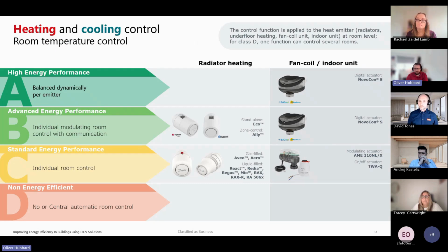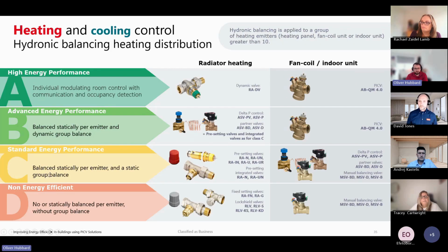So here we have a breakdown of what is actually in the actuator range and where they sit in terms of the new building automation and control standards. Things like the NovoCon actuators are in band A, smart TRV sensors in band B, and regular TRVs, thermal actuators or standard ABQM actuators are in band C. And when you look at it from the valve point of view, the dynamic balancing valves are in band A, and as you go down, you get back to regular TRVs and manual balancing valves.